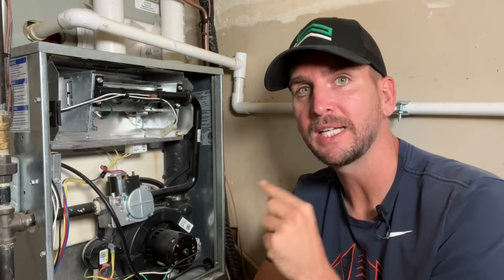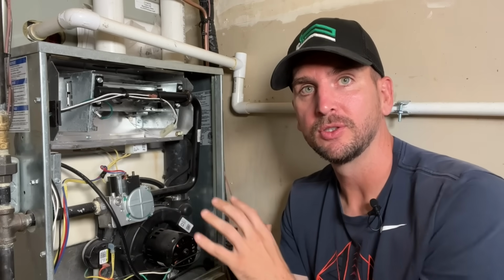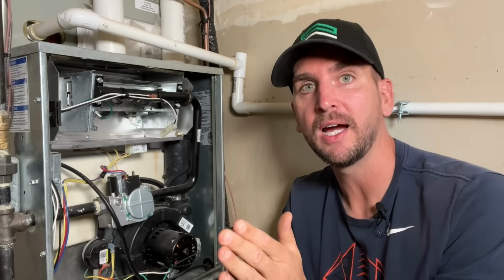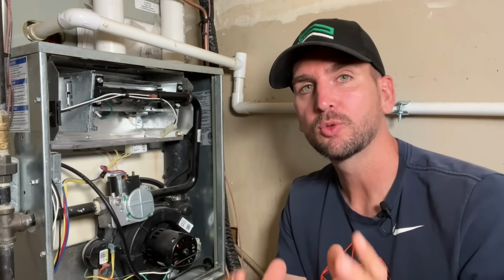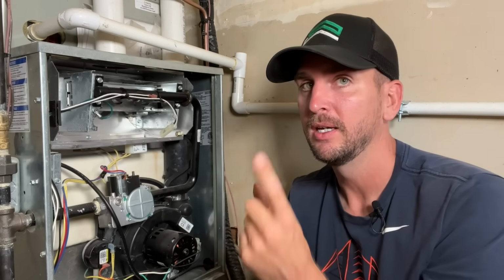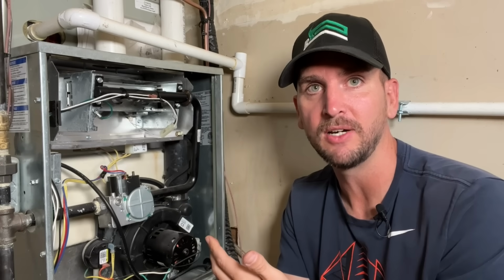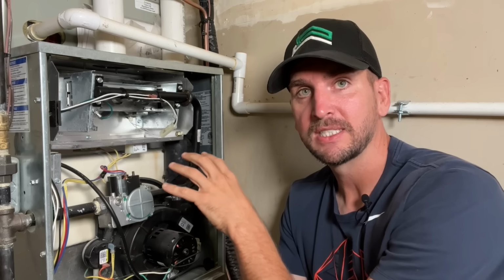Now your furnace will cycle through this condition, but then after 3, 4, or 5 cycles, your furnace will go into a lockout mode. Now that lockout will go on for hours as a safety protocol, because what's happening here is we're getting to step 5, and if you remember, step 5 was confirming that we have a flame. Right now, we're not able to confirm we have a flame, so the safety system is turning it off because you wouldn't want your gas valve open with gas being delivered inside your furnace or inside your environment, but no flame being lit. That obviously can be a dangerous scenario.